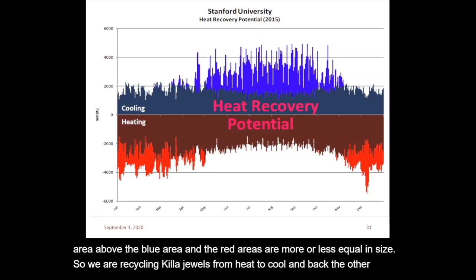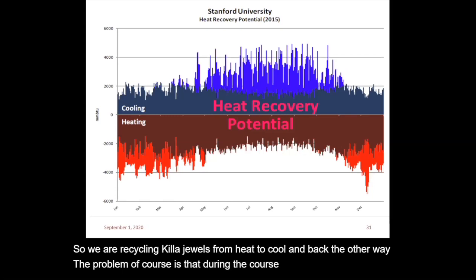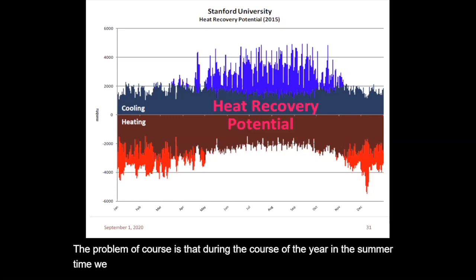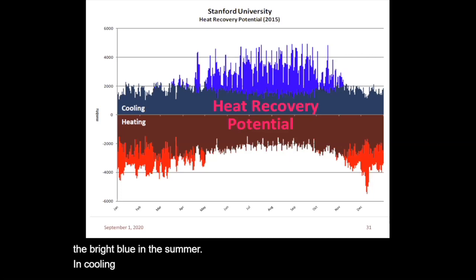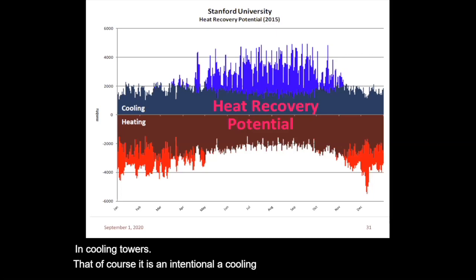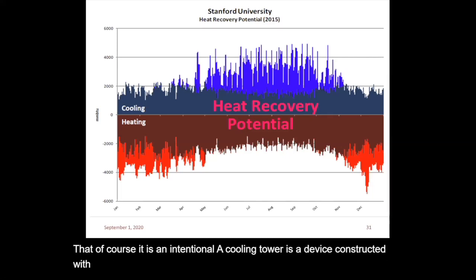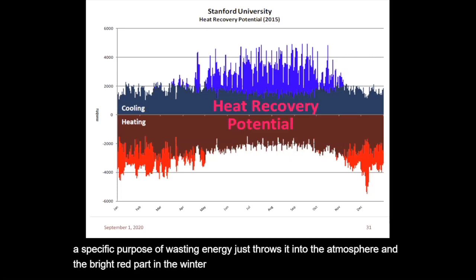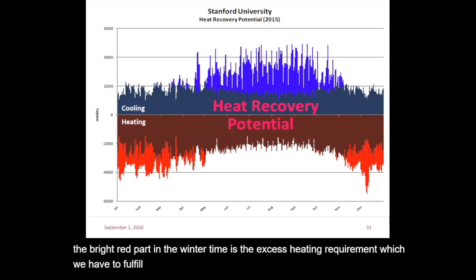The problem is that during the summer we have too much heat, so we have to dissipate the bright blue excess in cooling towers—a cooling tower is a device built specifically to waste energy, throwing it into the atmosphere. The bright red part in wintertime is the excess heating requirement for campus, currently met with natural gas.